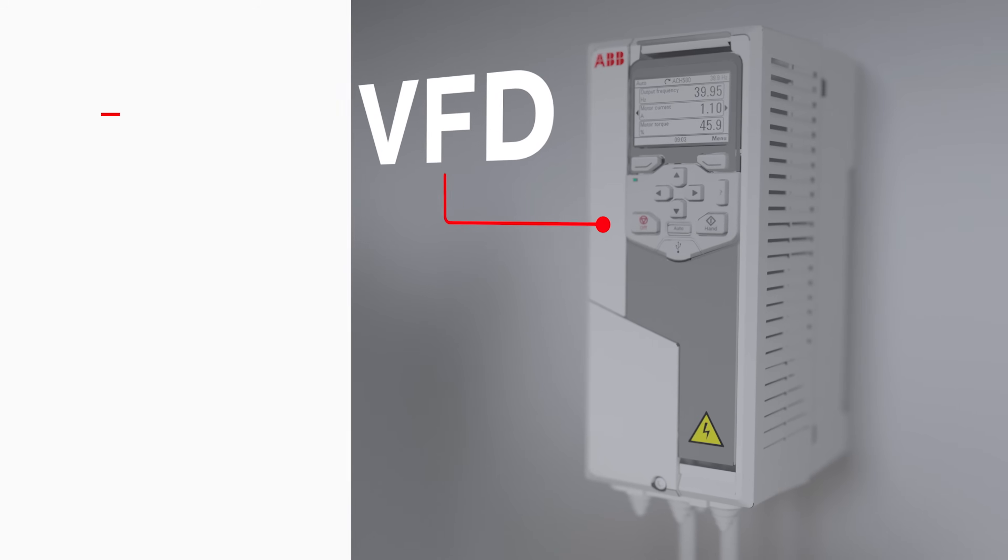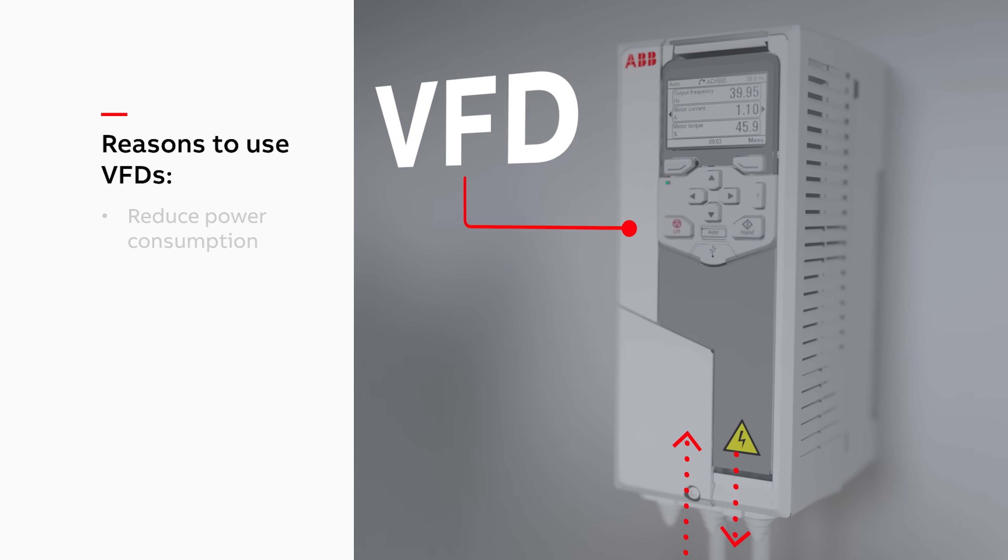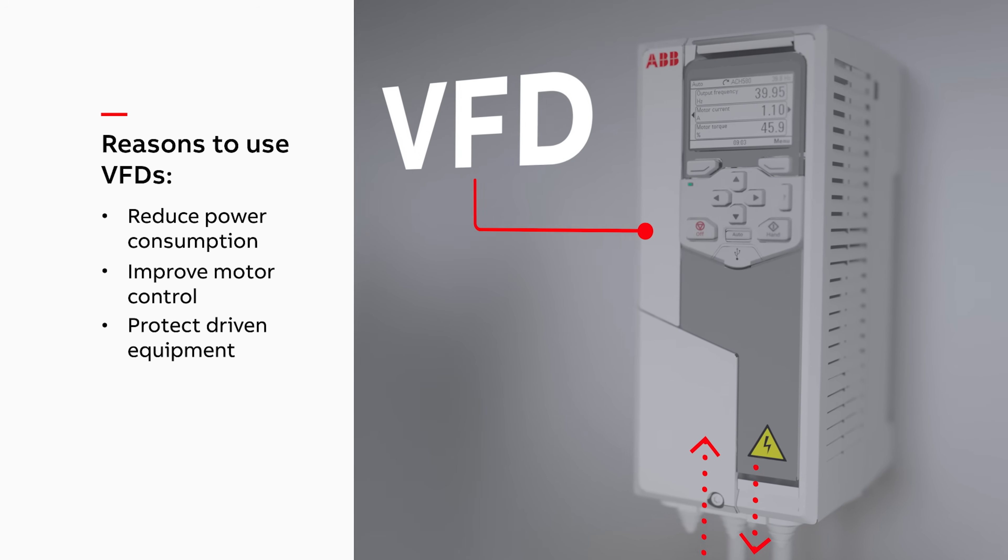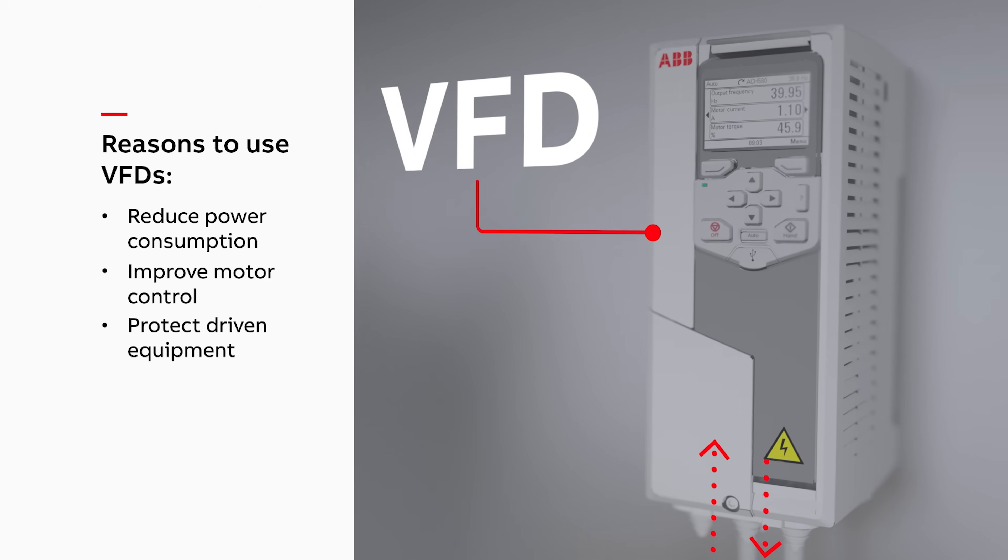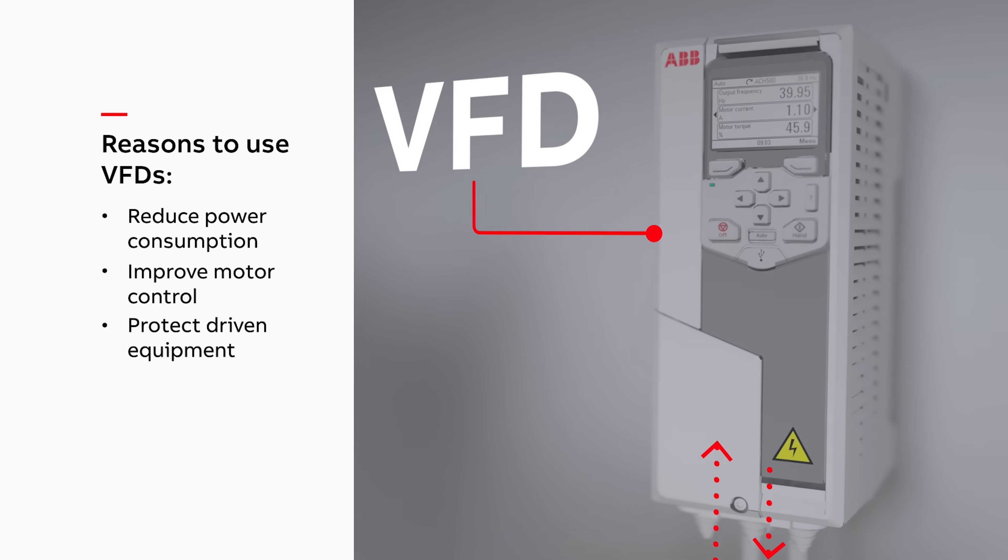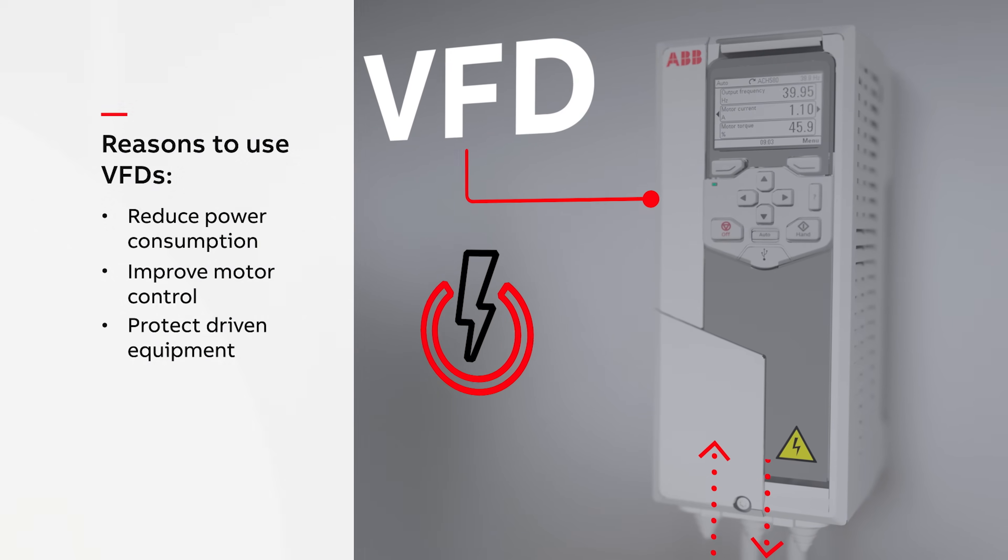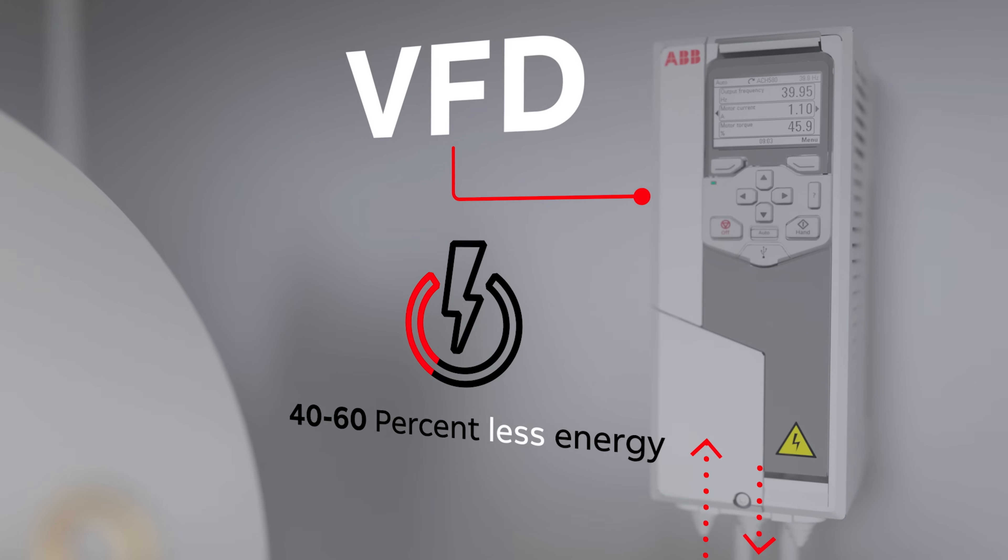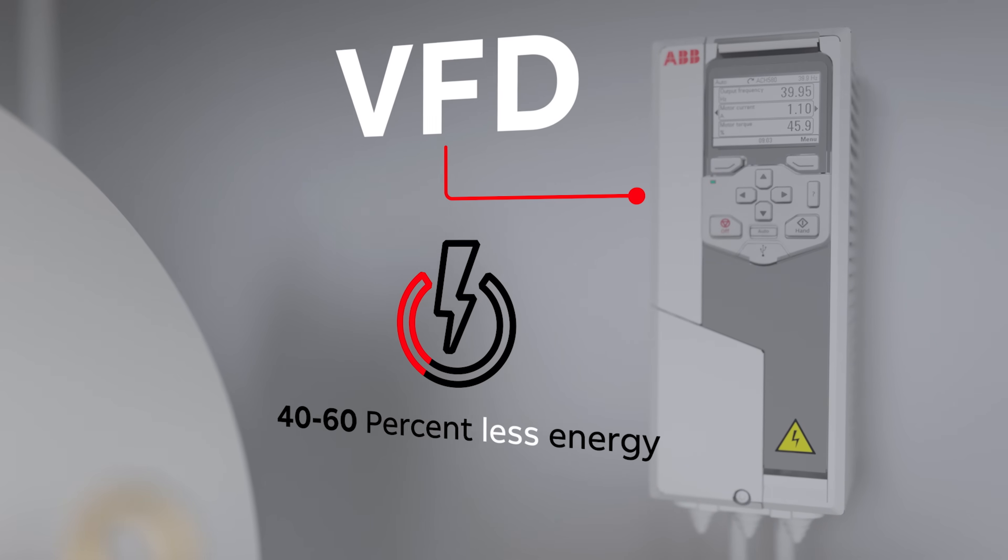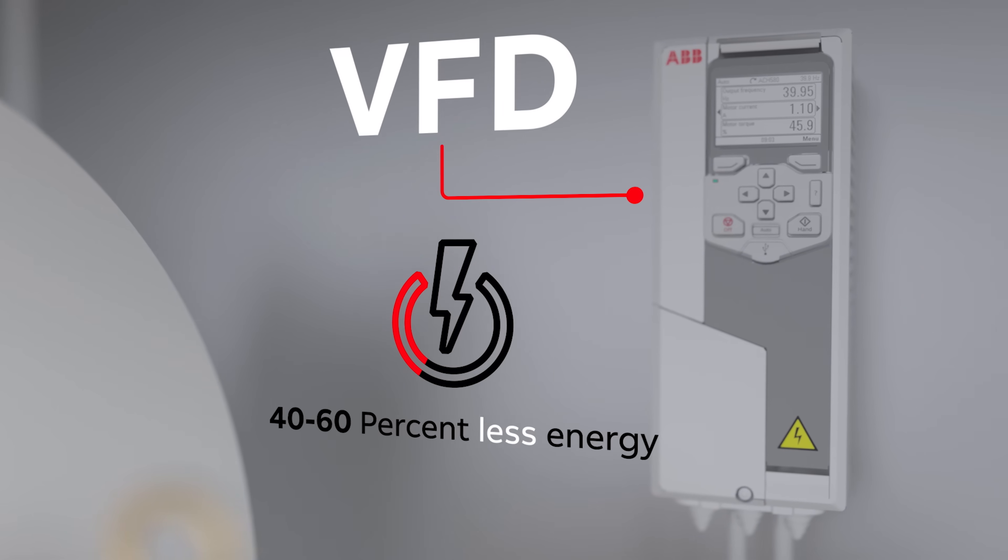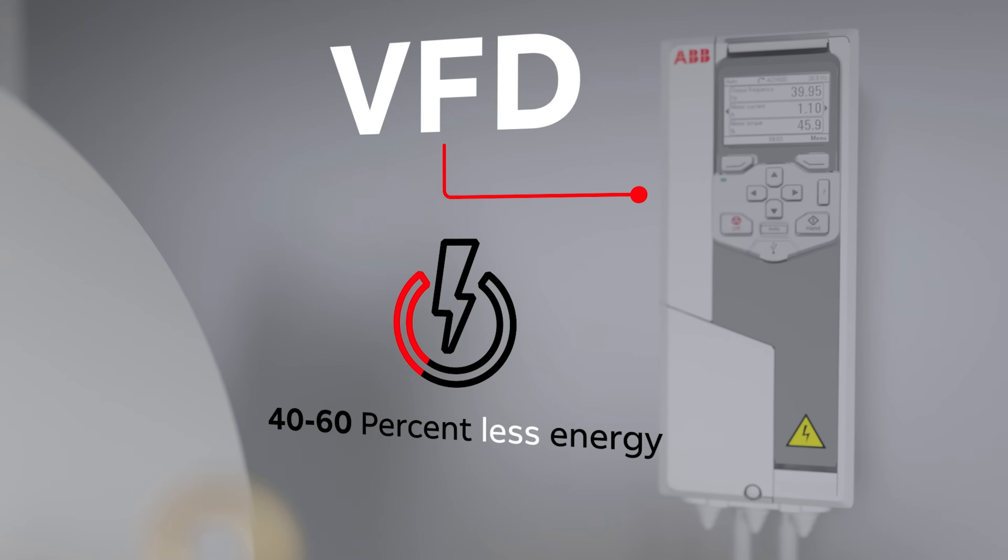VFDs control the frequency and voltage of the electricity that's fed to the motor and the equipment it powers. By removing the mechanical means of speed control, a motor system controlled by a drive uses 40-60% less energy. However, certain issues are presented when energy is controlled through a drive versus directly.